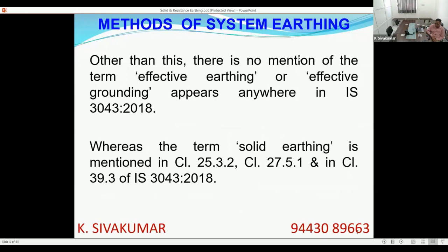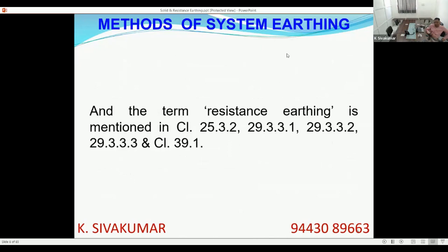On the other hand, if you search for the term solid earthing, it is mentioned in more clauses: 25.3.2, 27.5.1 and 39.3. So Indian Standard 3043 prefers to use the term solid earthing rather than effective earthing. And for resistance earthing, if you search, Indian Standard 3043 mentions resistance earthing in various clauses: 25.3.2, 29.3.3.1, 29.3.3.2, 29.3.3.3 and 39.1. So the Indian Standard, IS 3043, does not per se explain effective earthing or non-effective earthing. It says solid earthing and resistance earthing.